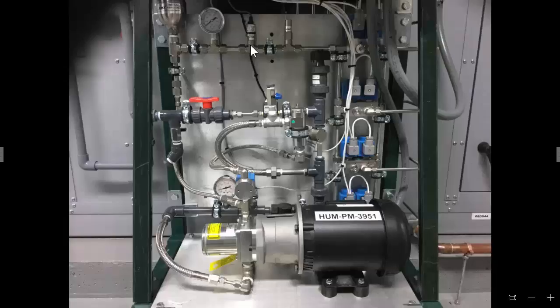So that goes back up into the microcontroller, which monitors it for high pressure alarms and low pressure alarms. A high pressure alarm would be if something happens that restricts the flow out of the unit and the pump wants to continue to pump. It will build up, and the set point of this is 1200 psi, and if it exceeds 1200 psi for 5 seconds, it will shut the unit down.